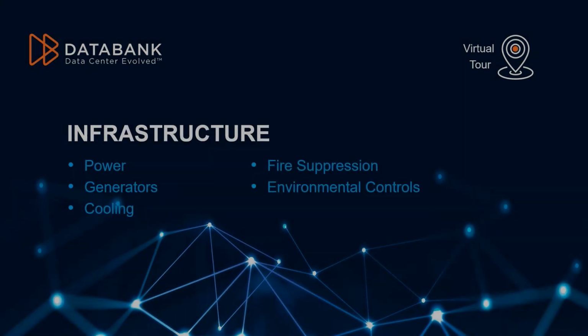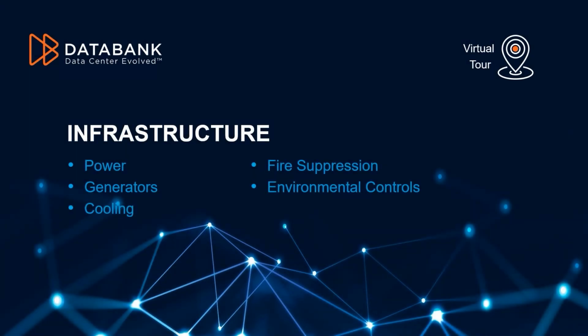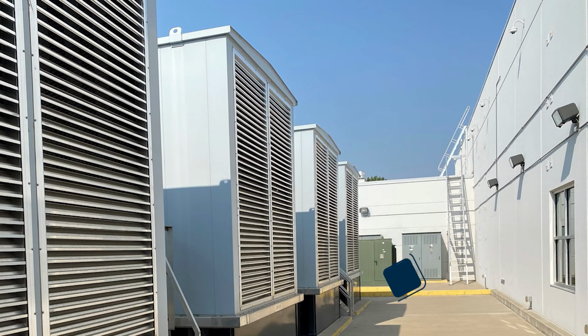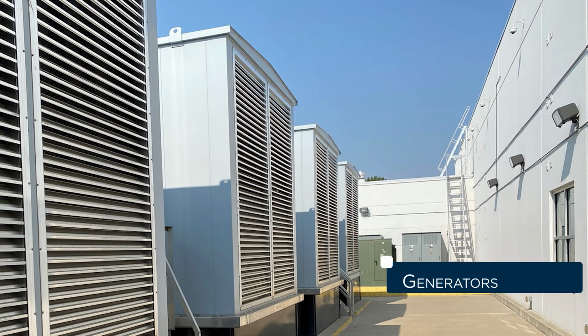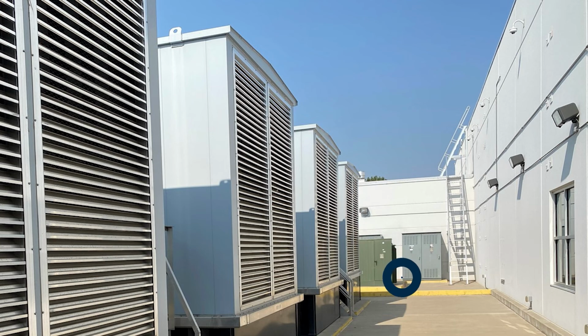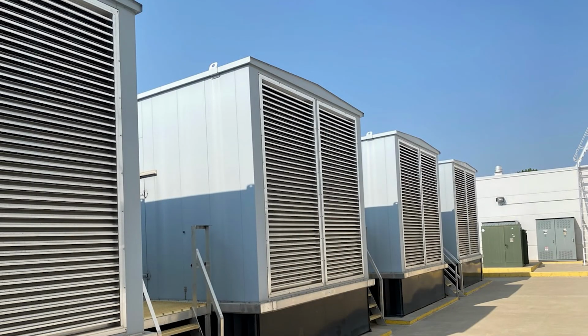The power transformers, generators, and cooling systems are in the equipment yard, which is protected by a 22-foot high concrete wall. A pumped refrigerant system is used because it eliminates water in the data halls and is very energy efficient in this climate. The system is modular, which limits the effect on cold air delivery in case of a condenser failure. We have deployed a modular design that provides 1.5 megawatt power blocks for IT load. The 1.6 megawatt diesel generators are in protective cases for noise reduction and protection against weather.